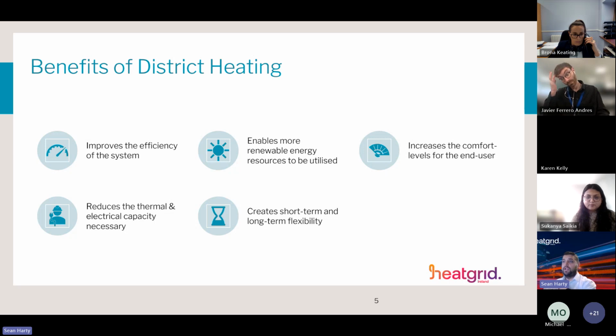It reduces thermal and electrical capacity demands, which is probably an important one. Because we're managing a number of heat loads, our base load is much higher and there's much less of a peak when it comes to peak heating load of a building. So we can size our heat pump based on the base load, which helps it run more efficiently since that load is much higher, and the peaks are much smaller and more manageable. Through employing thermal storage or even peaker boilers, you can manage that peak much more efficiently than with a single standalone heat pump.